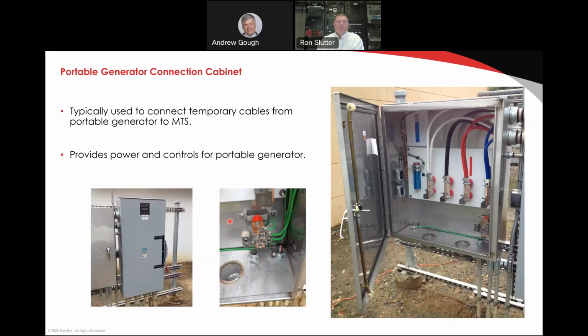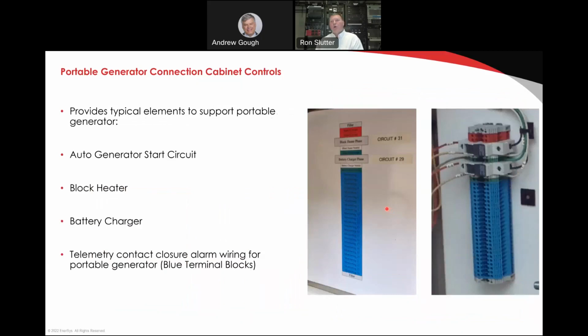As we look at each piece, you can see we have a separate ground bar, we have a neutral bar, we have the 3 phases. In this case, it's a 3-phase connection. We have a terminal block. That terminal block houses the standard needs for a portable generator. So if you needed to use that automatic start feature, all of those capabilities for the actual control of the portable generator are located on the terminal block and the portable generator connection cabinet. So here's kind of the blow up of that particular piece of equipment.